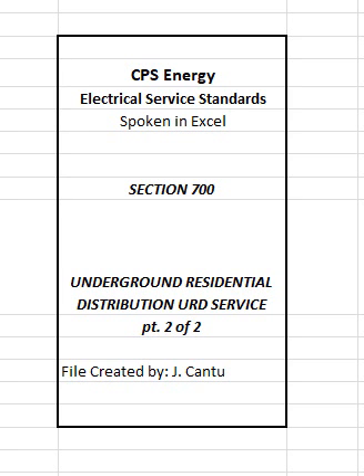704 Number of conduits. Only one conduit for service lateral conductors will be permitted, and conduit shall contain the 2 ungrounded, phase, conductors and 1 neutral conductor. Exception: additional conduits that may need to be utilized for larger loads or duplexes will require prior approval from CPS Energy.